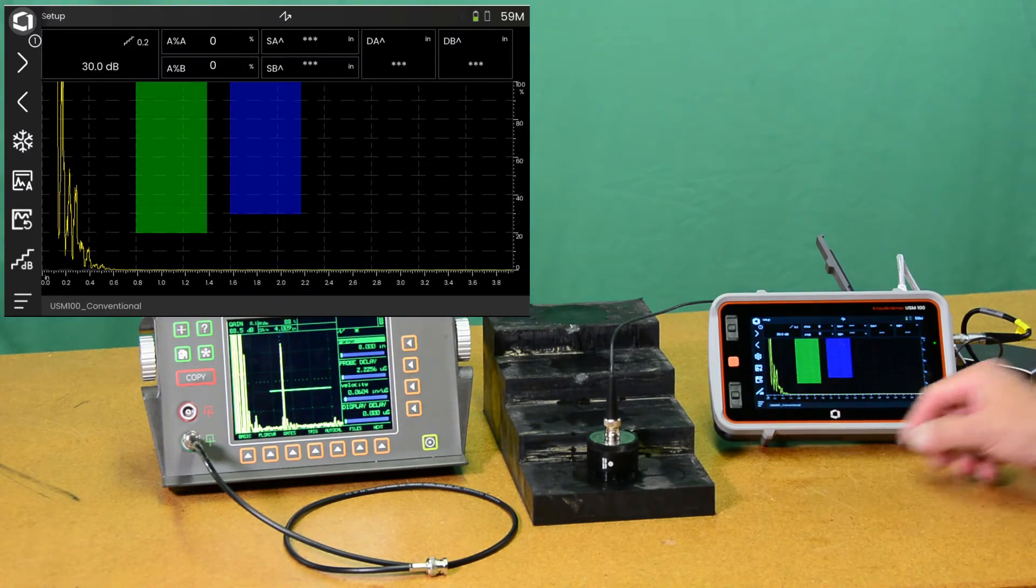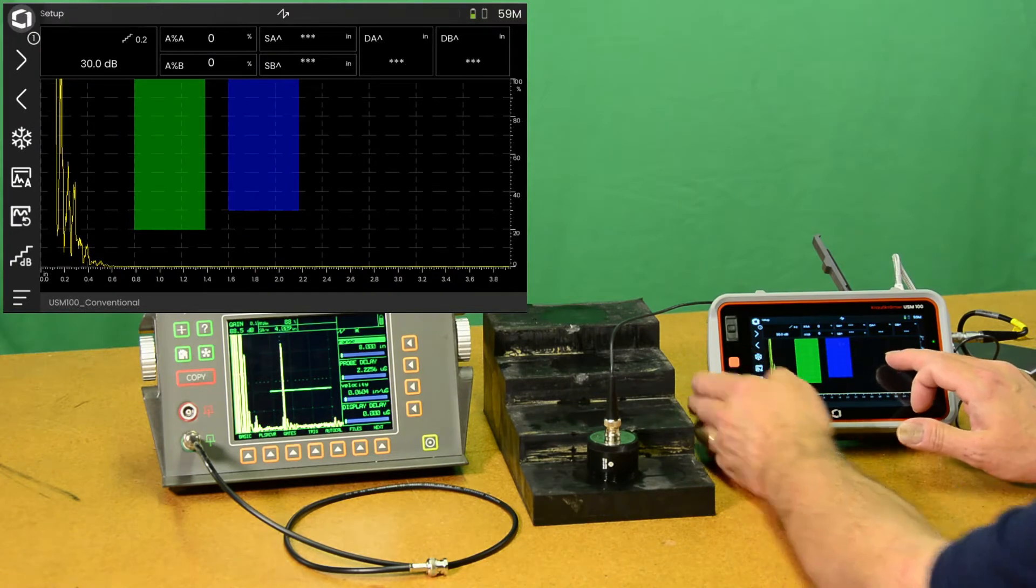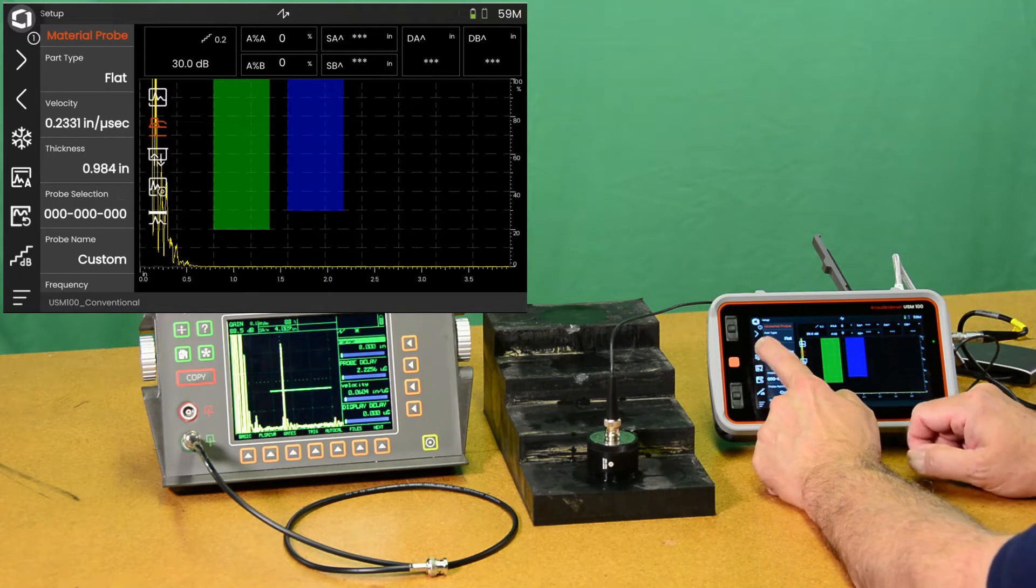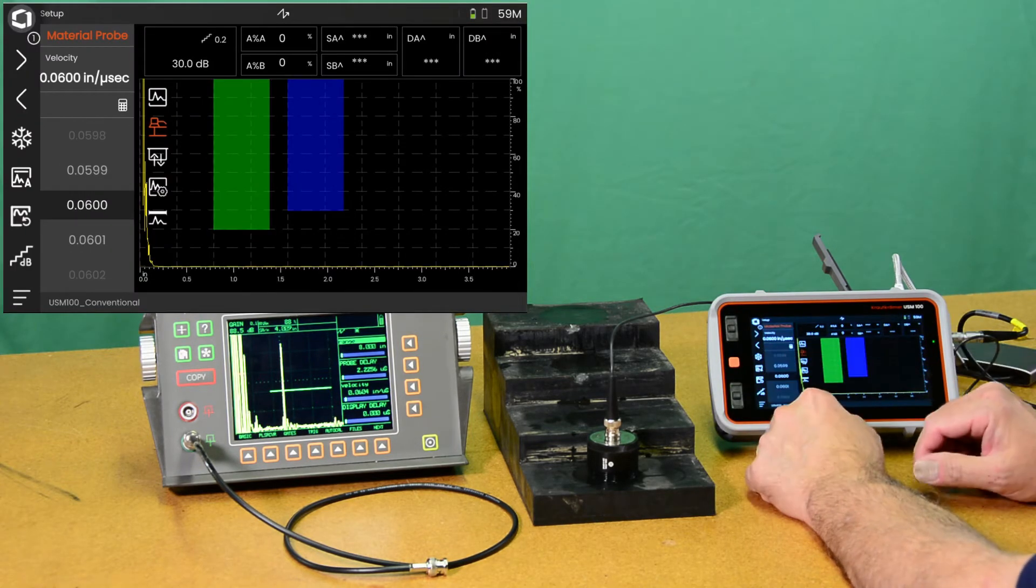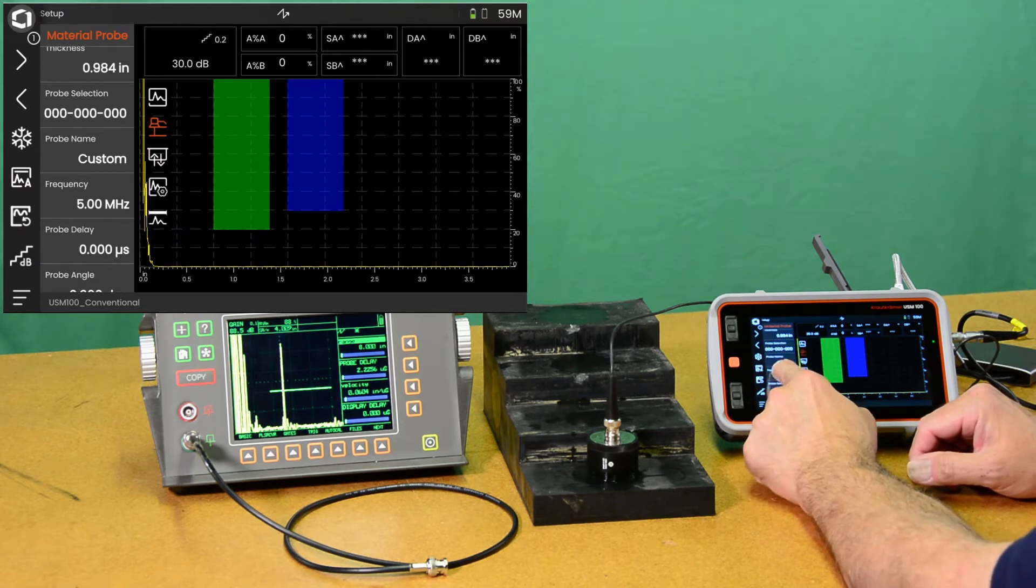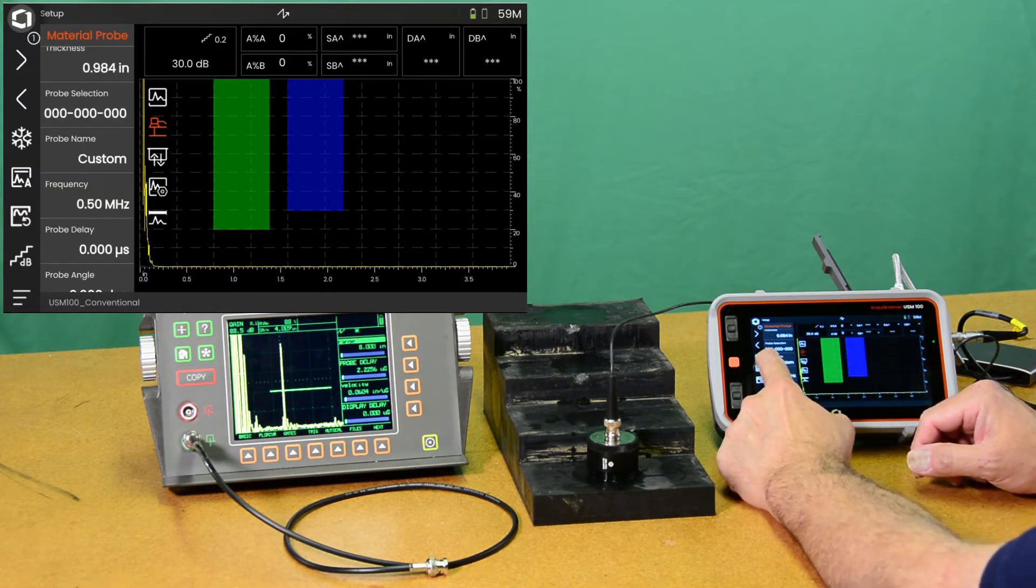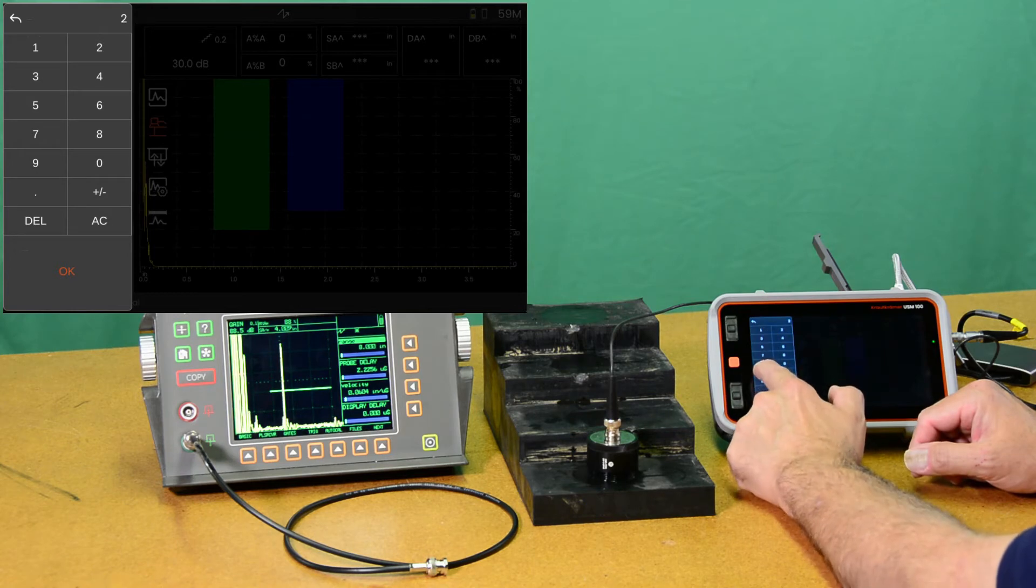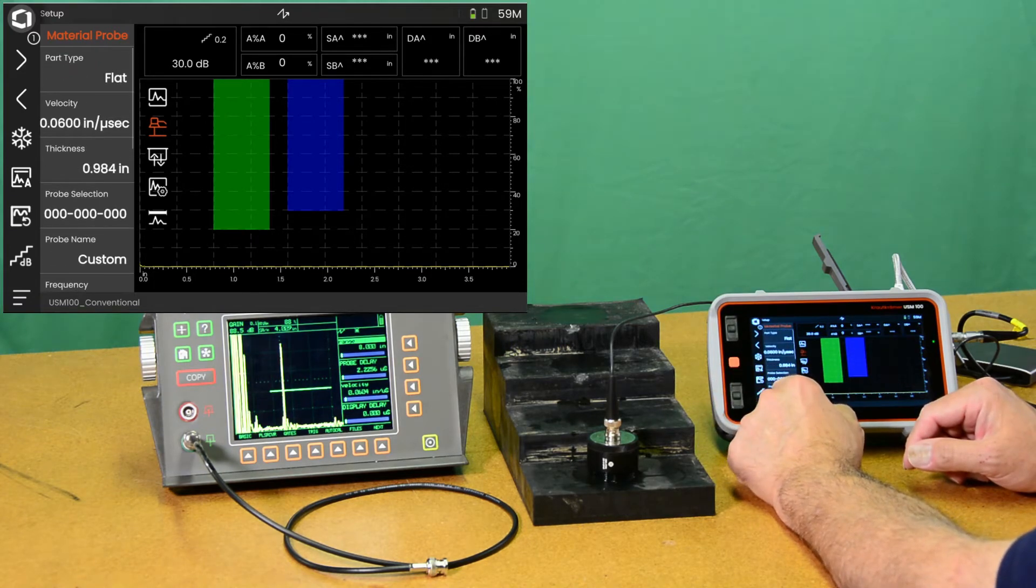First thing we're going to do is come in and set up the probe. I touch the A-scan to open the menus and choose the probe menu to start. We have a flat part. We're going to set our velocity to 0.06 inches per microsecond. I happen to know that the rubber is approximately 0.06 inches per microsecond velocity. We're going to tell it that the probe frequency is 0.5 megahertz. We're going to tell it that the probe delay is approximately 2.3 microseconds.